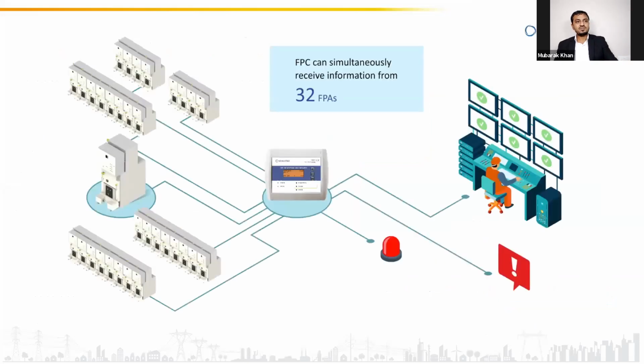Just to visualize in a broader manner, all the switchgears will be connected together through RS-485 communication. All this data will be transmitted to the FPC. FPC will communicate it to the control system, as well as give a local annunciation or control. It can communicate to SCADA, or it can send an SMS to the duty staff. Up to 32 FPAs can be connected to one FPC.